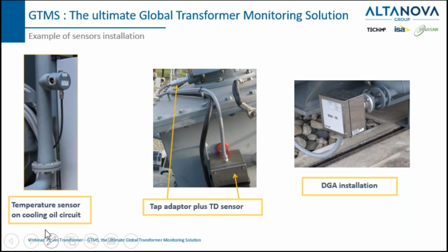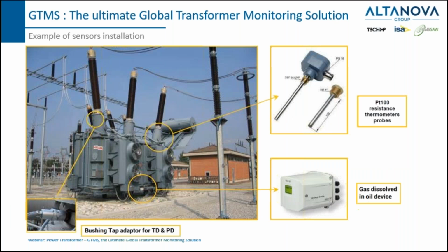Here, some examples of sensor installation. On the left, you have a temperature sensor on the cooling oil circuit. In the middle, you can see an example of installation of a tap adapter sensor plus the TD sensor here below. And on the right, a simple 2 gases DGA unit. All these components are connected to the same hub, the Global Transformer Monitoring System hub. These are other examples of sensor installation. This is another type of tap adapter. In this case, we have PT100 resistance thermometers, and another type of DGA.